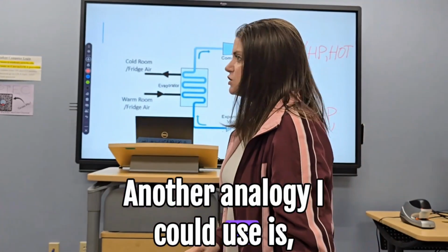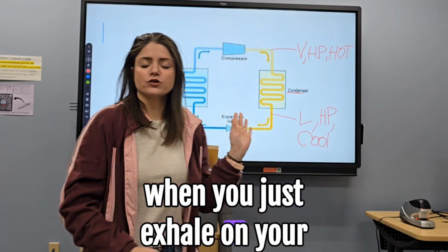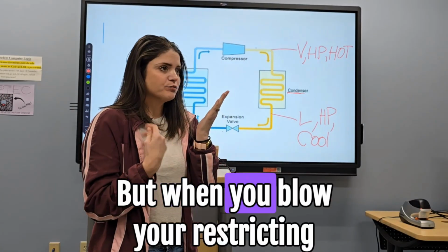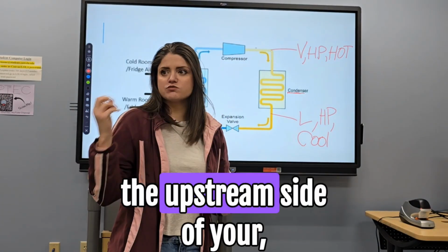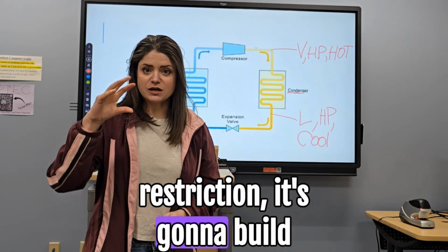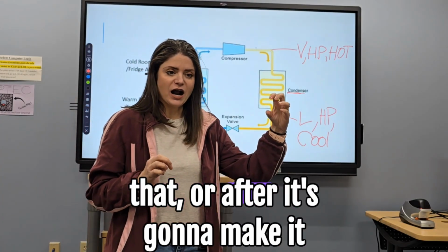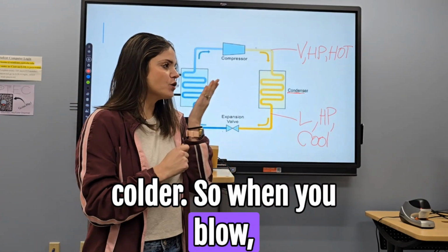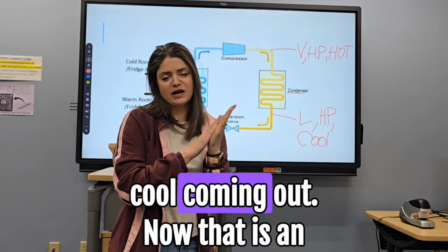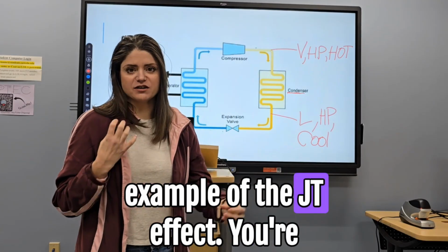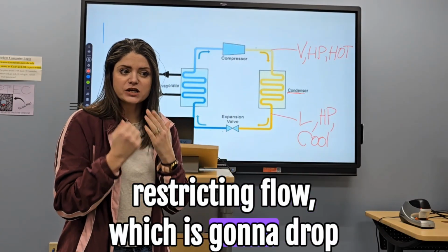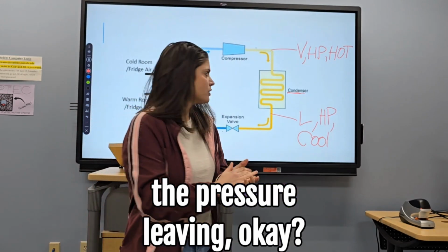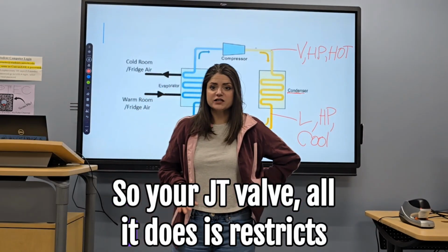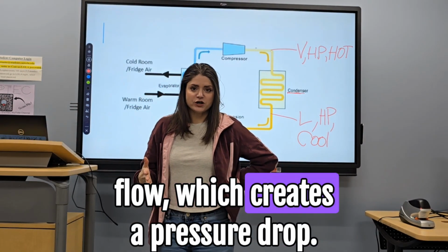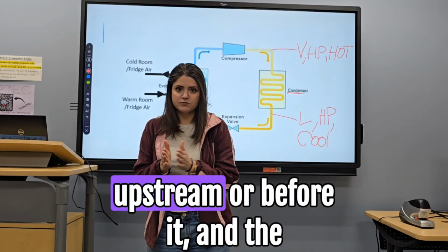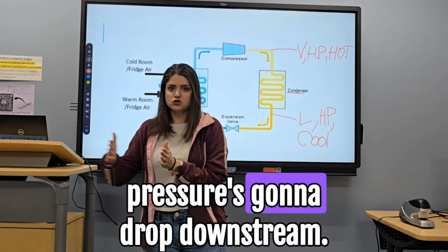Another analogy I could use is when you just exhale on your palm. It's warm, right? Well, when you blow, you're restricting flow. The upstream side of your restriction is going to build pressure, and downstream, or after, it's going to be colder. So when you blow, all of a sudden it's cool coming out now. That is an example of the JT effect. You're restricting flow, which is going to drop the pressure leaving. Okay. So your JT valve, all it does is restrict flow, which creates a pressure drop. Your pressure is going to build upstream or before it, and the pressure is going to drop downstream.